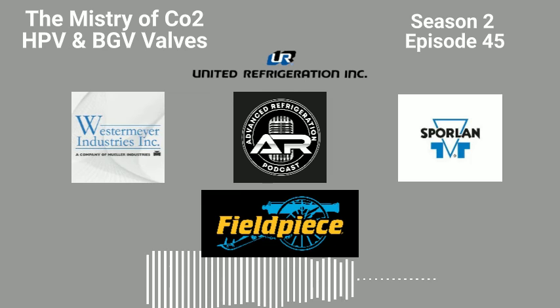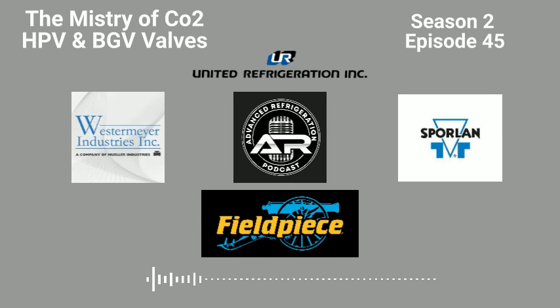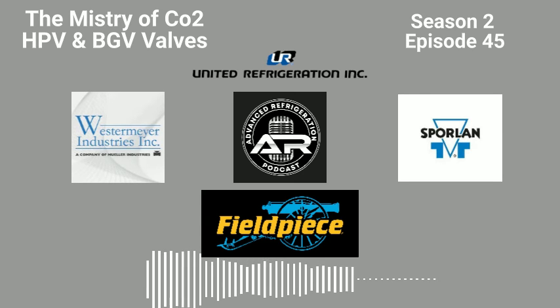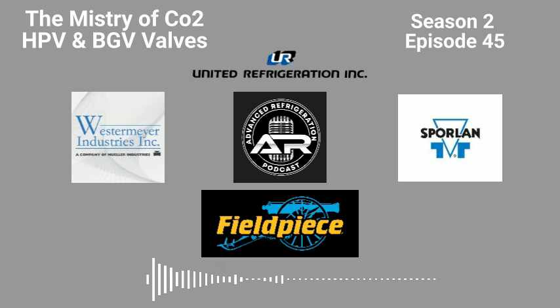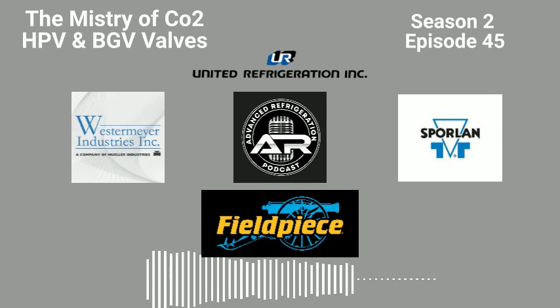Now, me personally, I think the whole enable is just ridiculous. Just get rid of it. It is not needed. You don't ever need to enable or disable that controller because it's going to do it on its own. If the rack shuts down and the flash tank starts to creep up, it's going to instantly slam those valves shut.